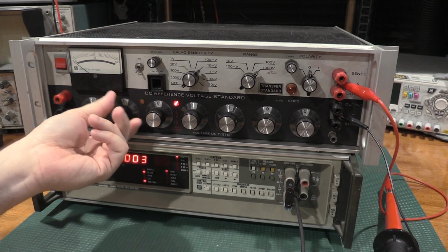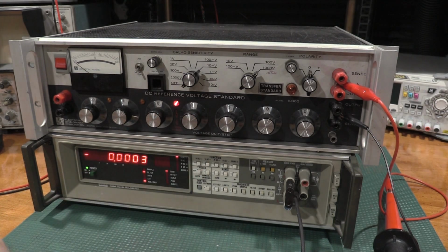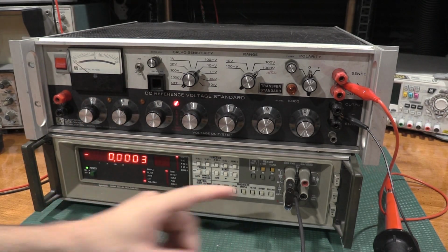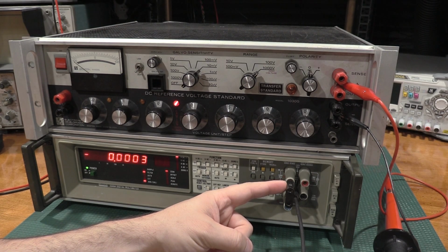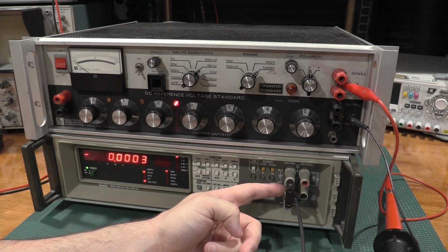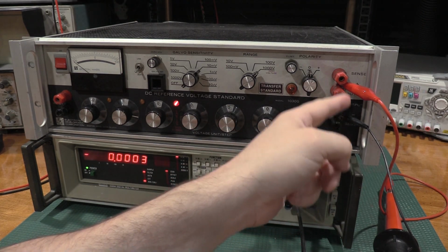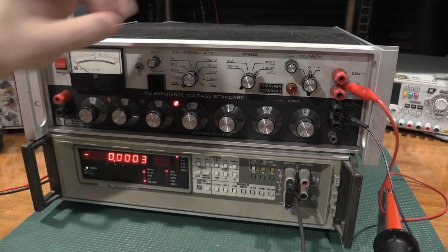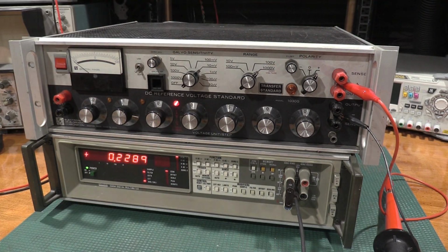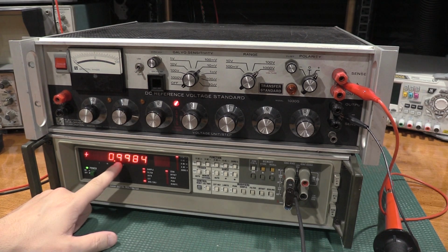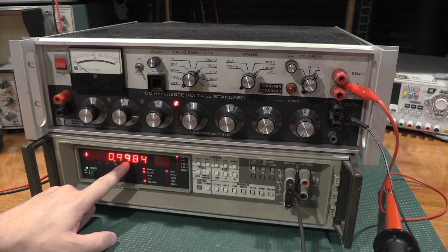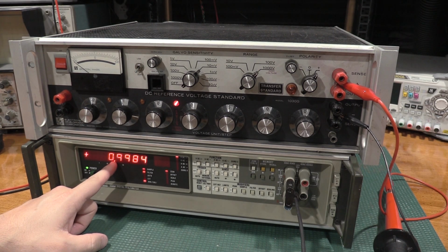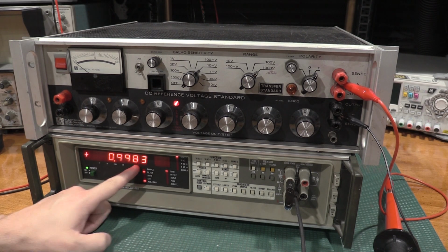Oh, that knob's off. Have to adjust that. The high voltage probe is hooked up, making sure the ground leg is on the meter ground. Ground clip was hooked up first, then the power connector, and then we kick this on. Give the meter a chance to stabilize. And this is what we get. So 0.9984 volts. You multiply that by 1,000. So what the meter's saying is 998.3.